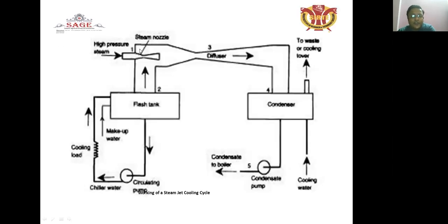This is the diagram showing how the steam jet cooling system works. The flash tank, steam nozzle, diffuser, condenser, condensate to the boiler, condensate pump, cooling water, the waste or cooling tower. This is the chilled water circulating to the cooling load. Here, the high pressure steam enters the steam nozzle, increasing the velocity, and after that it passes through the diffuser where kinetic energy is converted to pressure energy.